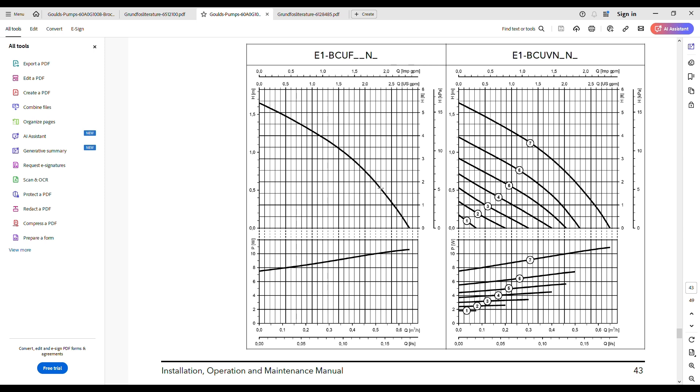If you're flowing too much liquid or not enough, you can have what they call cavitation, which is bad for the life of the pump, as I said. So anyway, I put that valve in in order to throttle the flow, slow the flow down, and get rid of this potential cavitation problem.